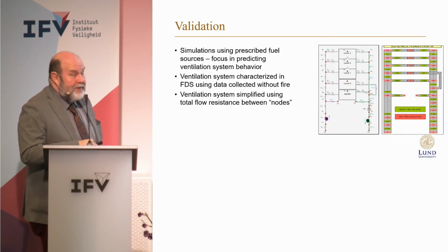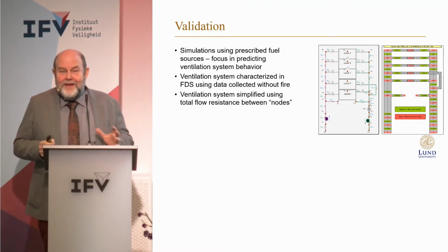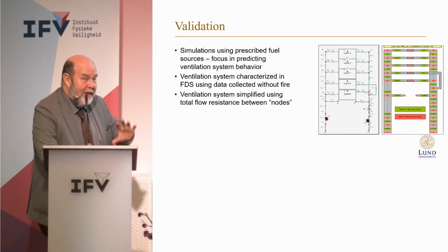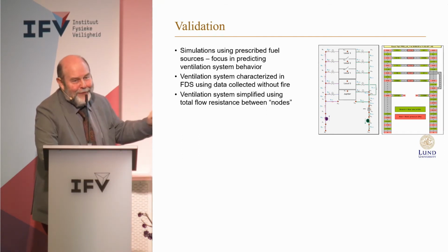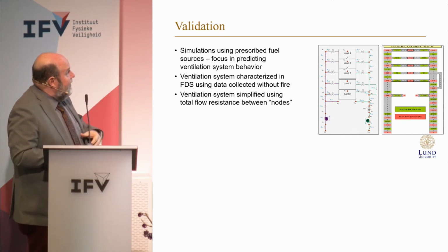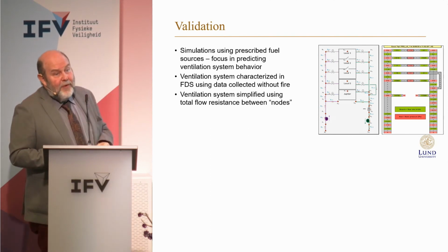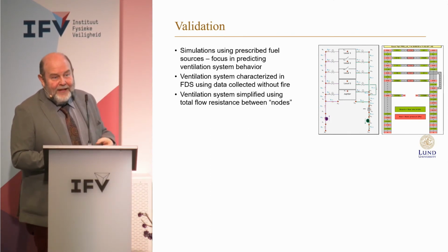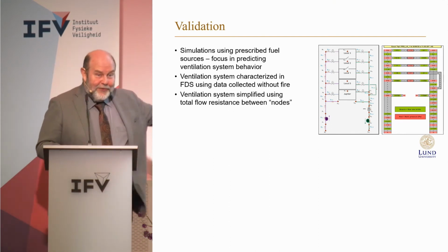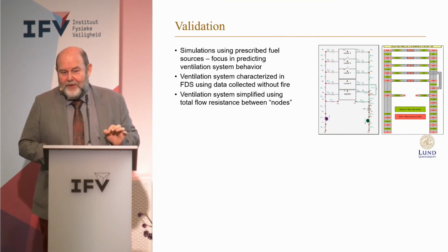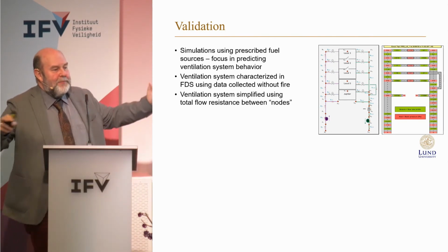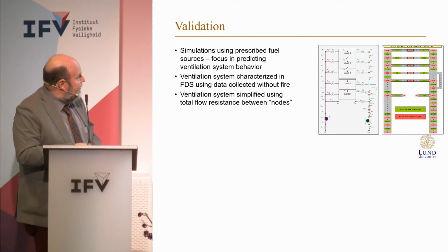I don't expect you to understand it, but this is a bit the so-called mechanical ventilation system. And there's maybe a few ventilation engineers here, but it has, as I said, a complex system. And for the modeling, I'm afraid to say that, you have to get that into your model. And that's not maybe the easiest and user-friendly part which FDS has now, because FDS has a so-called HVAC module, which is a ventilation model, but it is not as user-friendly as the rest of FDS. So it's hands-on. It's typing in the nodes. I can say that my PhD student suffered a lot to get that into the system, but it was the only way, to be honest, to get the prediction which was acceptable. Otherwise, it was a bit like we started in the beginning. You get this spread of results depending on how you had solved the problem.